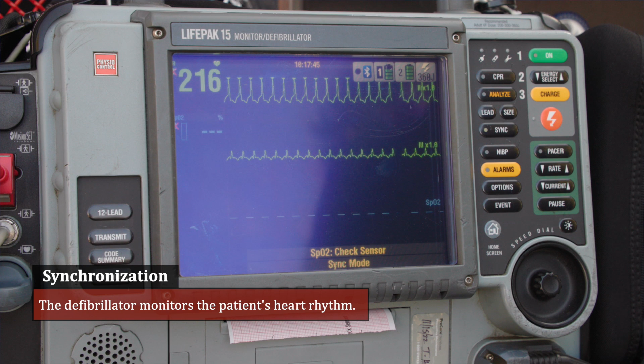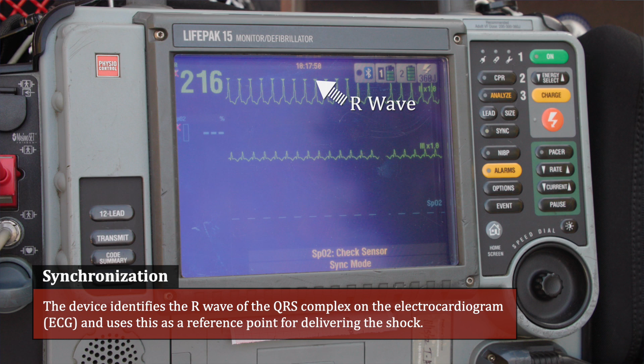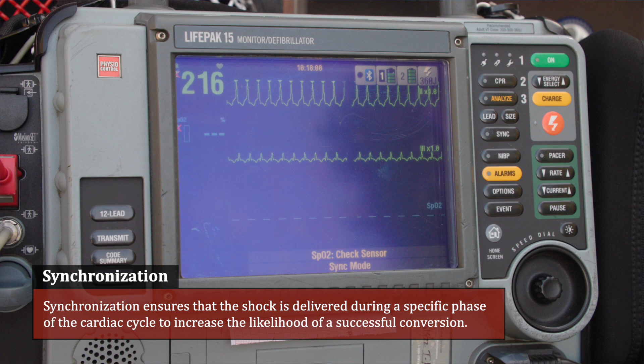The defibrillator monitors the patient's heart rhythm. The device identifies the R wave of the QRS complex of the electrocardiogram and uses this as a reference point for delivering the shock. Synchronization ensures that the shock is delivered during a specific phase of the cardiac cycle to increase the likelihood of a successful conversion.